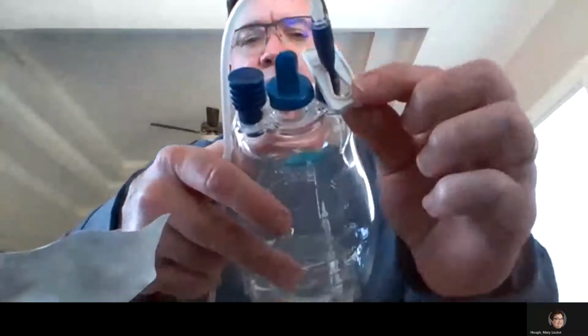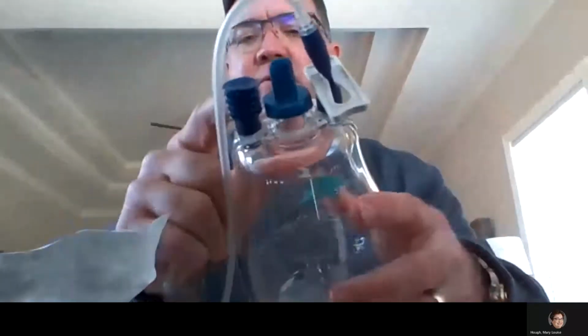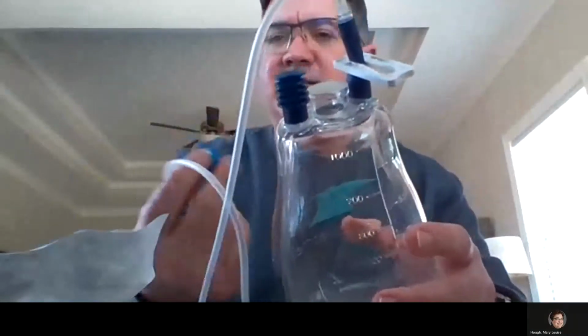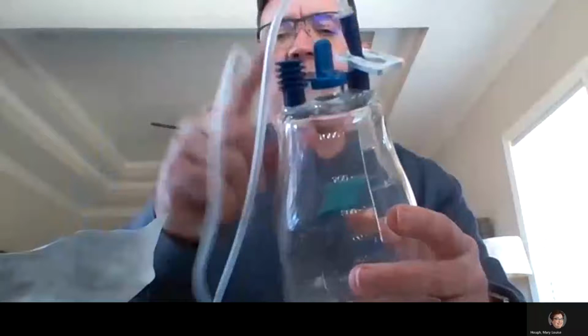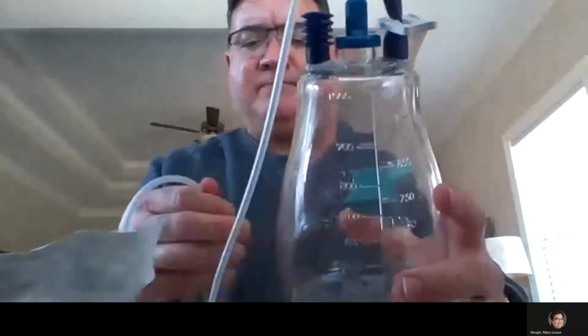So we have the vacuum indicator. Here on the top, we have our drainage line with a slide clamp, just easy on and off. Everybody knows how to use that. And then finally here in the middle is a little tab. So once I'm done draining, I can take this tab off, and there's a foil seal here. If I turn this tab over, I can puncture that seal, take my bottle, dump that down the toilet, and then double bag it into a Walmart or Target bag and throw it right in the garbage. It also allows me to get access to the fluid if for any reason I need to take a sample or anything like that. So these are 3 unique things to Rocket that we have on our bottles. And as I said, our extra long cable here to give you that room.